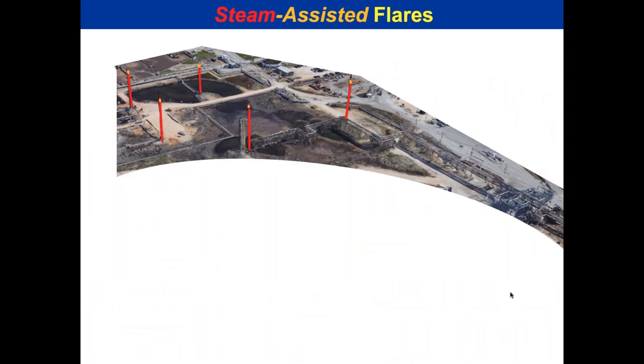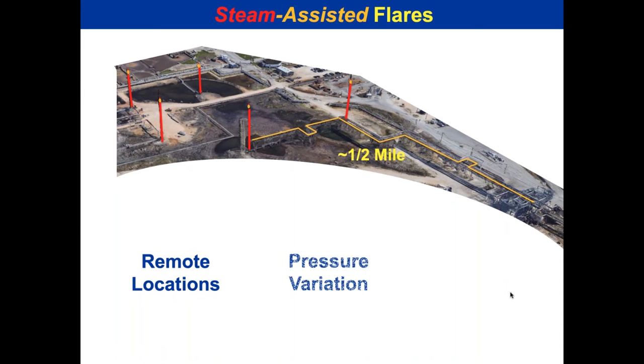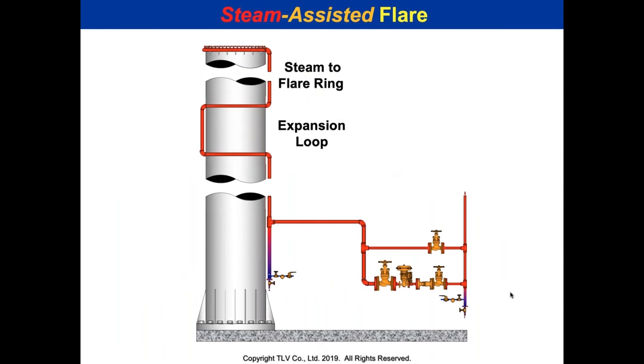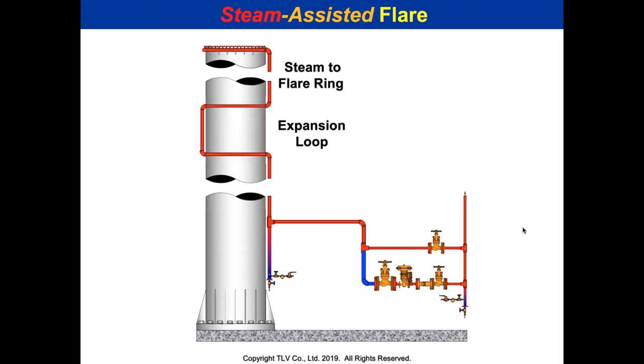You can look at flare systems on Google Earth — they can be a half mile walk out or more. Remote locations have pressure variations from flaring to non-flaring and load variations. Looking at a graphic: you see the flare tower, the steam line going up, and the control valve station. The problem is the bypass line — when bypassing, steam flows fine, but condensate builds up in the control valve line with no trap to drain it. When the control valve opens, you send a slug right up to the tip. The simple fix is a trap station there.